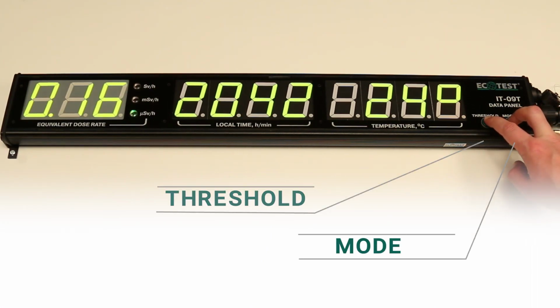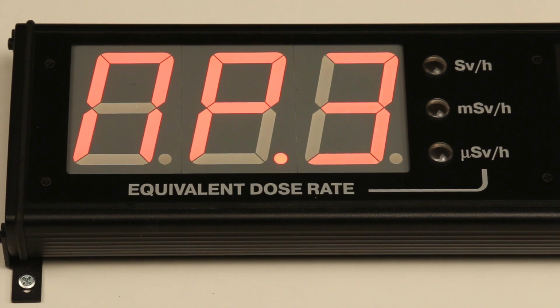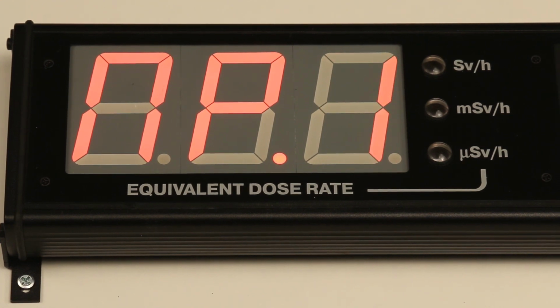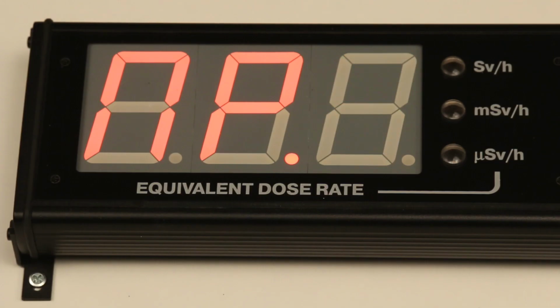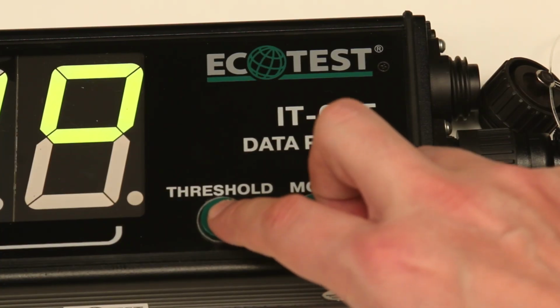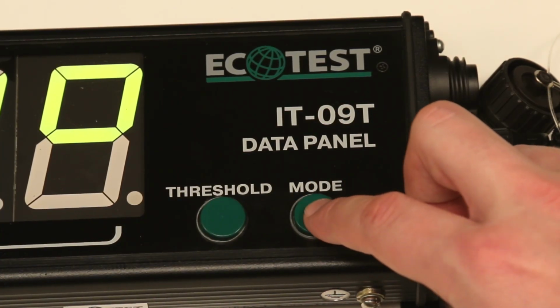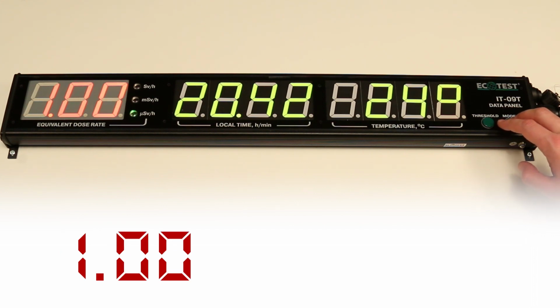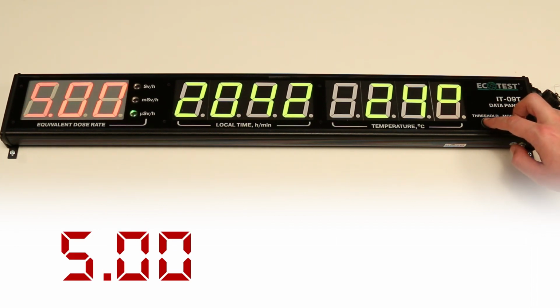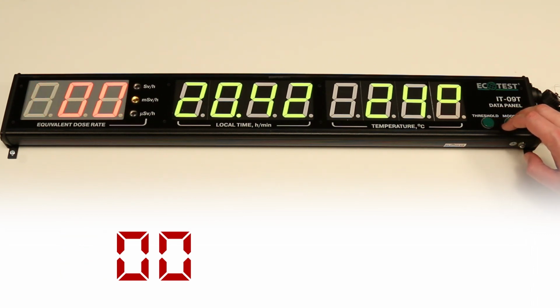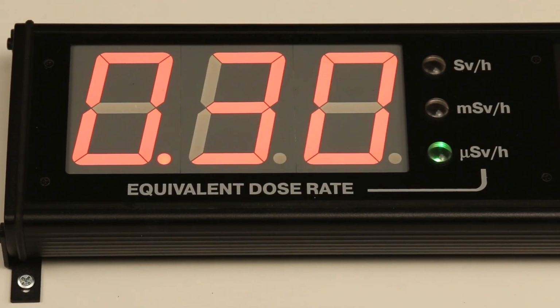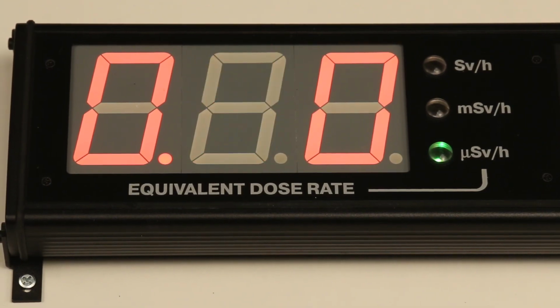Press threshold and mode at the same time and hold them until the red dotted symbols appear on the display. Then release both buttons. Two red symbols will appear on the gamma radiation dose rate indicator and a threshold level number, a blinking digit from 1 to 3. To change the number, press shortly mode. Select a threshold number and press mode. The least significant digits of the threshold level value are displayed on the dose rate indicator, and the least significant digit of the dose rate indicator is blinking. This confirms that the value of the digit position can be changed.